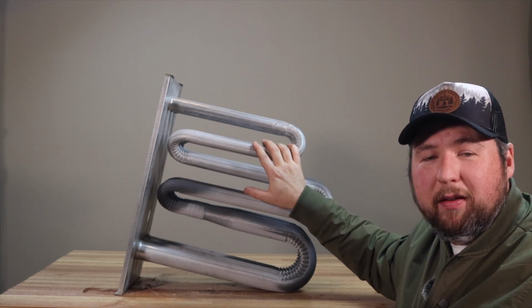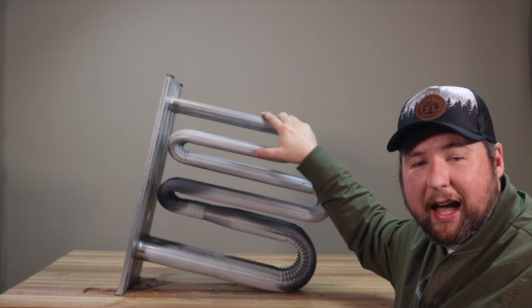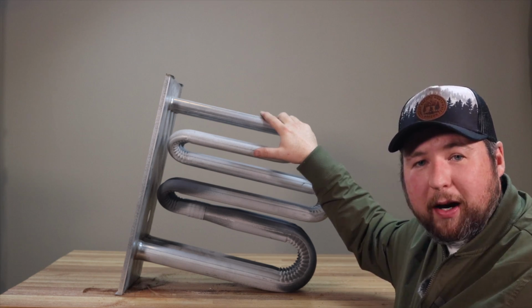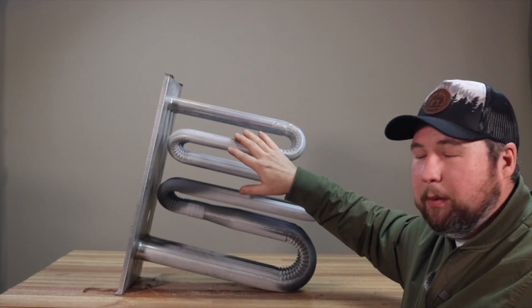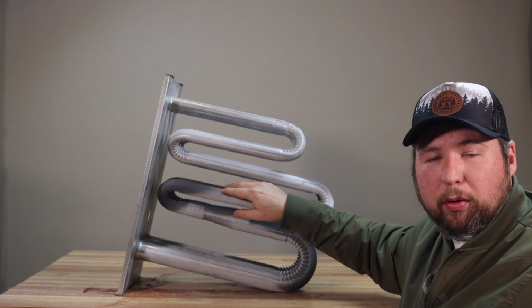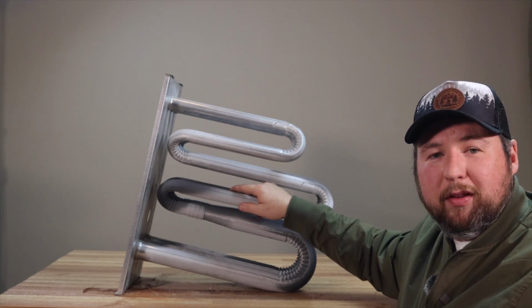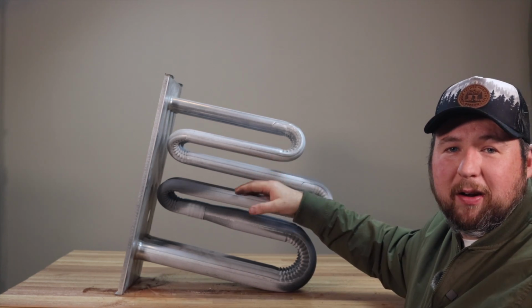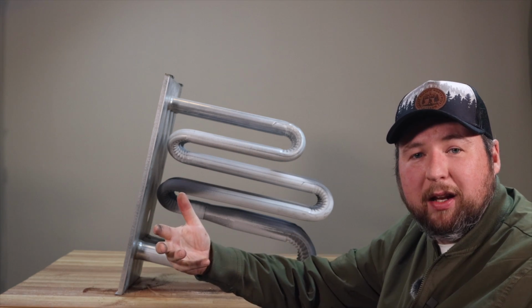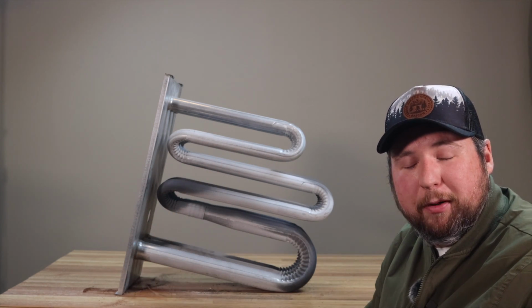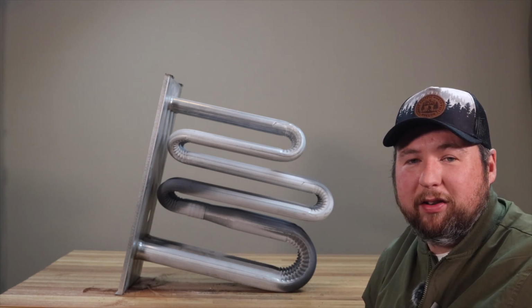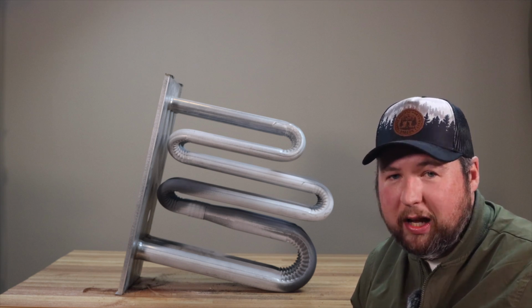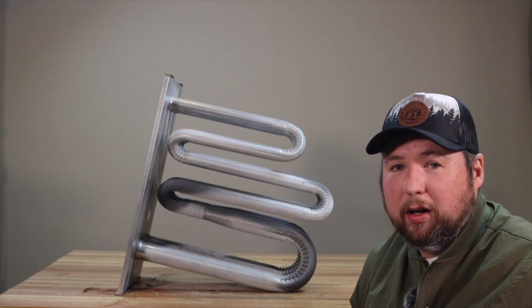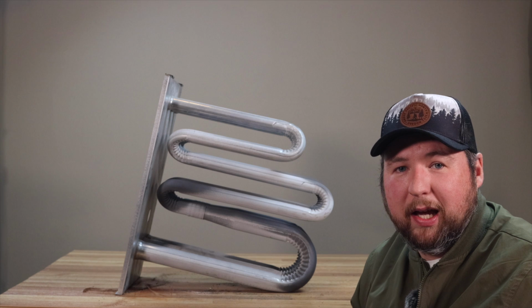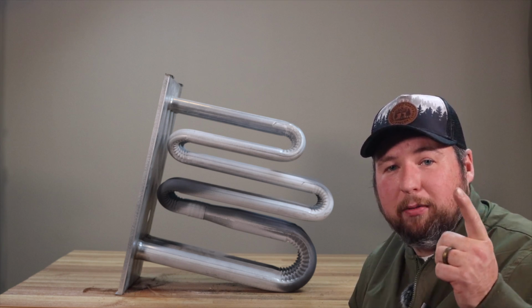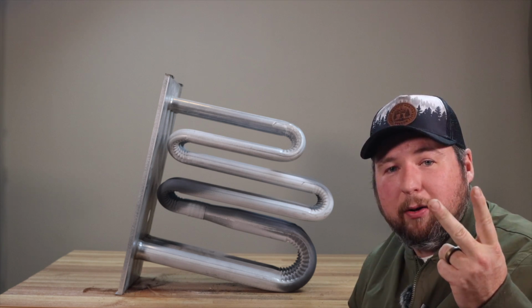The main point of this thing is to keep all your combustion gases isolated from your airstream. If this becomes compromised, where a hole or a crack forms, those gases could possibly get into your airstream, and now you're breathing it in your home, and it becomes a potential hazard. If you find a compromised heat exchanger, depending on your state or your country, you're going to shut it off and tell the customer, you have two options. You can replace the heat exchanger, or you can replace the heater.